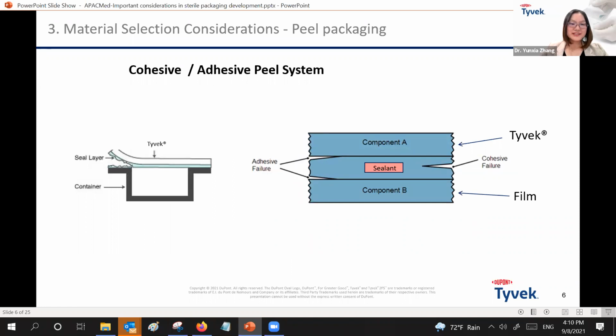Now let's move on to the material selection consideration. In case of a packaging made of a porous material, for example Tyvek, and a non-porous material, for example film, there is a need to introduce a sealant layer here. Normally there are two types of sealant on the market. First is adhesive sealant, and second is cohesive sealant. As you can see here, with the adhesive sealant, the seal and the peel function happen at the same point. But for cohesive sealant, it seals here, but it peels in between, inside the sealant.